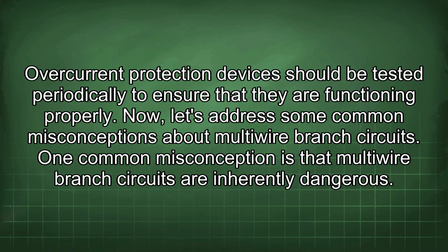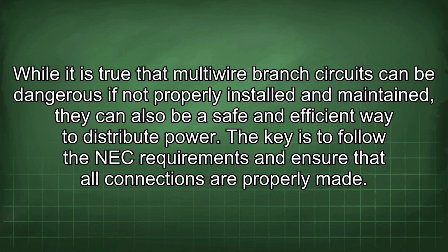Now let's address some common misconceptions about multi-wire branch circuits. One common misconception is that multi-wire branch circuits are inherently dangerous. While it is true that multi-wire branch circuits can be dangerous if not properly installed and maintained, they can also be a safe and efficient way to distribute power. The key is to follow the NEC requirements and ensure that all connections are properly made.